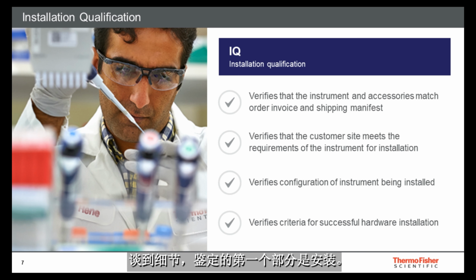Moving on to the details. The first component of a qualification is installation. By definition, the installation qualification will establish with confidence that process equipment and ancillary systems are installed to manufacturer's recommendations. Additional supporting details about installation instructions and test procedures can be found in section 820.170, Installation.